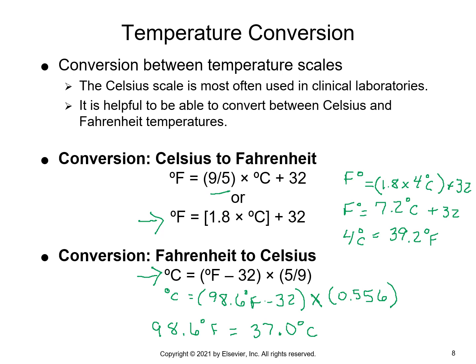So let's first talk about the temperature of 4 degrees Celsius. This is what a lot of your refrigerators in the lab are considered, the temperature that you want to maintain within a couple of degrees, depending on what department you're in. But let's just say for blood bank, the storage units that you keep the units of blood in, the large refrigerators, have to be somewhere around 4 degrees Celsius. So you don't want it to go too low because it could freeze things, and you don't want it to go too high because it could cause those blood units to warm up and not be preserved.